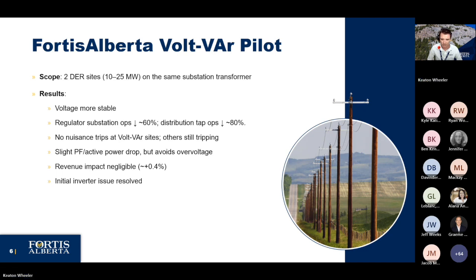So although the power factor and active power output under Volt-Var mode was slightly lower than the fixed power factor mode, Volt-Var mode has the potential to keep the voltage in the acceptable range, meaning that we were avoiding overvoltage trips. So as a result of that, we found that the net revenue from these particular projects had negligible impact. The actual number is about 0.4% higher than when they were in fixed power factor mode. But the point is that it wasn't a major issue.